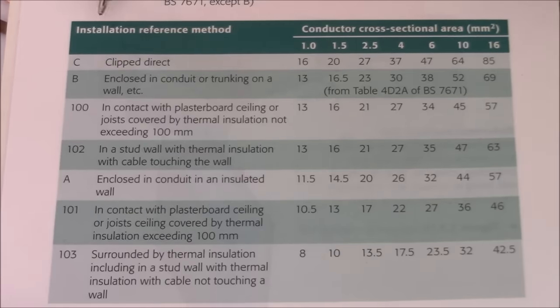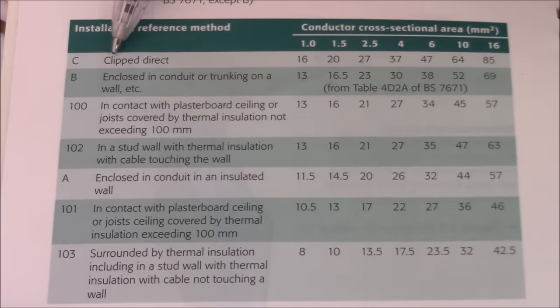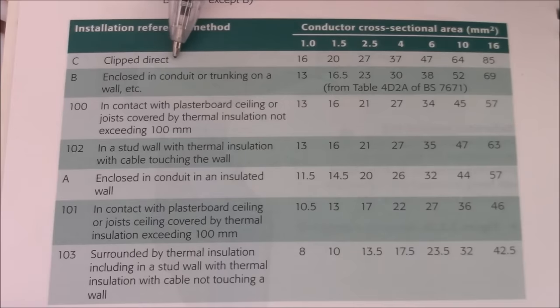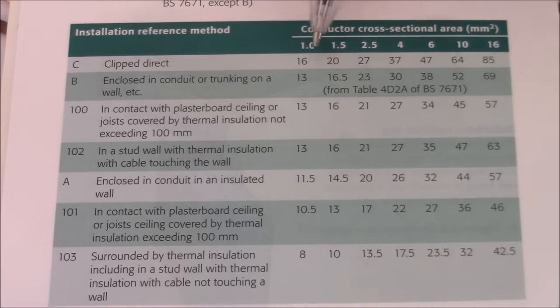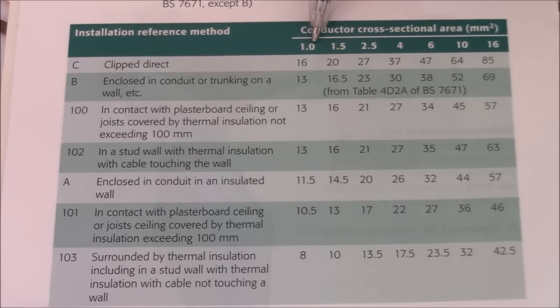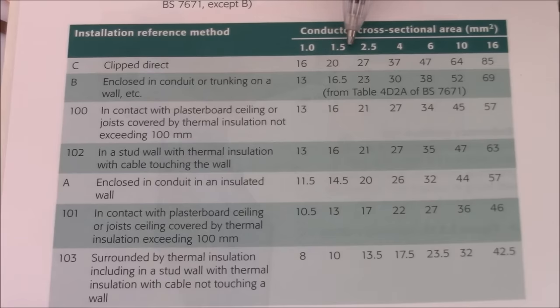Now on this side there's the installation reference method. So Clip Direct basically is when you clip the cable directly to the wall. And this is the rating for let's say 1 mm cable, 16 amp, 1.5, 20 amp, 2.5, 27 amp and so on.